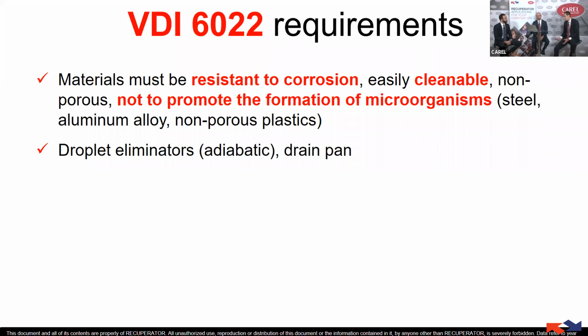We know that when we make adiabatic humidification, for example, we need drop eliminators in order to prevent non-evaporated water from passing through the AHU and going into the ventilation system, and from condensing in other parts of the AHU. It also suggests creating a properly drained pan to drain the water that we collect, that we retain through the droplet eliminators.